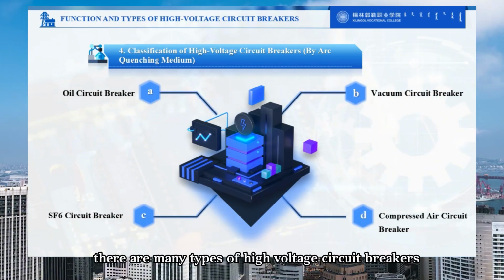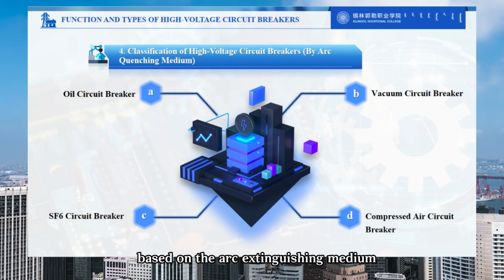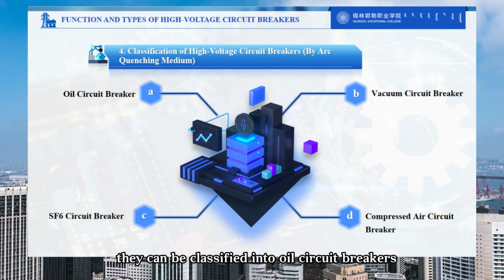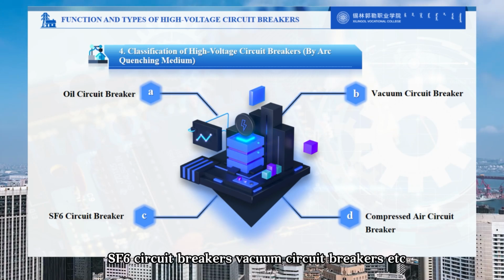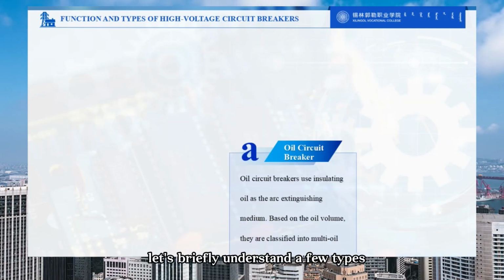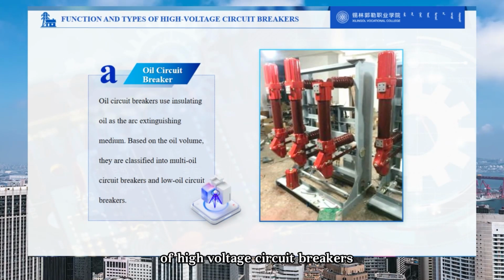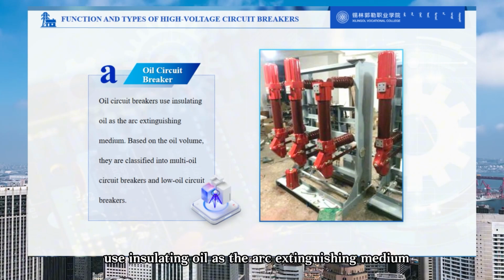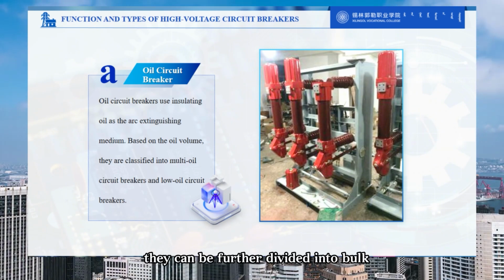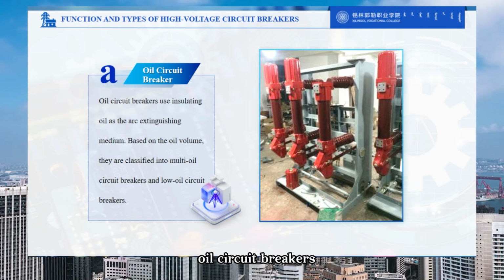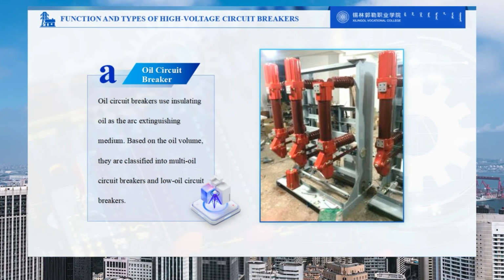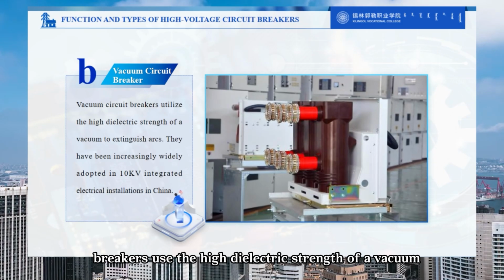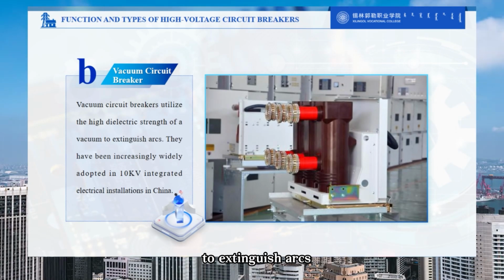There are many types of high-voltage circuit breakers. Based on the arc extinguishing medium, they can be classified into oil circuit breakers, compressed air circuit breakers, sulfur hexafluoride, SF6, circuit breakers, vacuum circuit breakers, etc. Let's briefly understand a few types of high-voltage circuit breakers. Oil circuit breakers use insulating oil as the arc extinguishing medium. Based on the amount of oil, they can be further divided into bulk oil circuit breakers and minimum oil circuit breakers. Vacuum circuit breakers use the high dielectric strength of a vacuum to extinguish arcs.